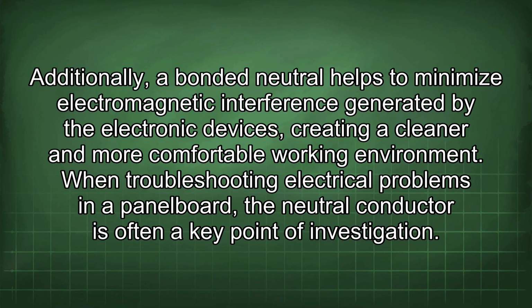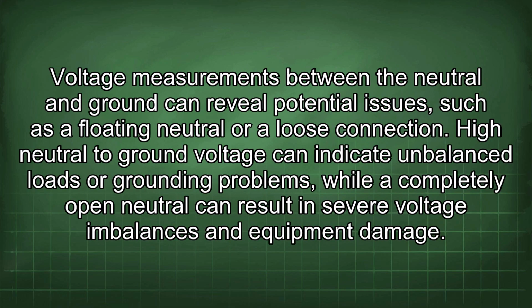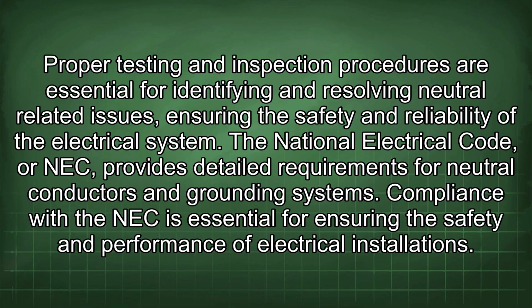When troubleshooting electrical problems in a panel board, the neutral conductor is often a key point of investigation. Voltage measurements between the neutral and ground can reveal potential issues, such as a floating neutral or loose connection. High neutral to ground voltage can indicate unbalanced loads or grounding problems, while a completely open neutral can result in severe voltage imbalances and equipment damage.